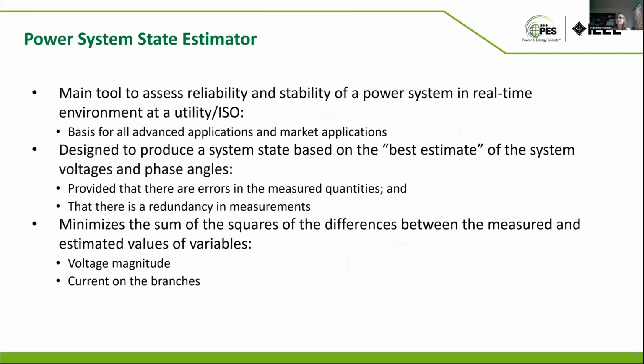It is designed to produce a system state based on the best estimates of the state variables, usually voltage magnitude and phase angles. The core calculation in many state estimators is minimizing the sum of the squares of the differences between the estimated and the measured values of variables. Next one.